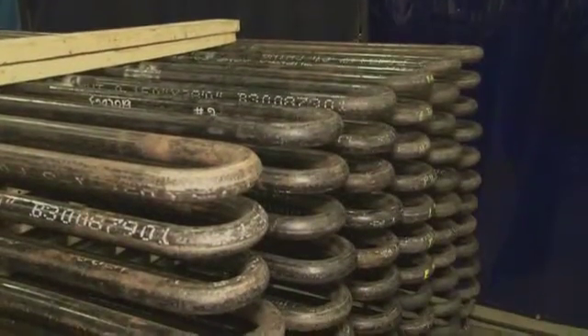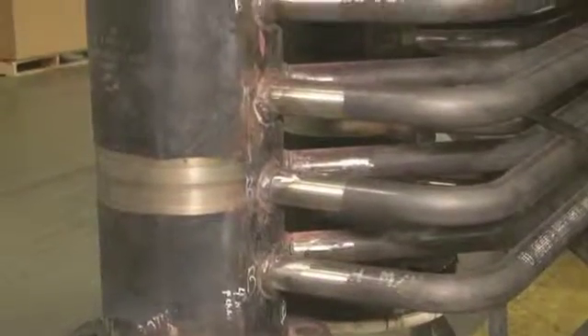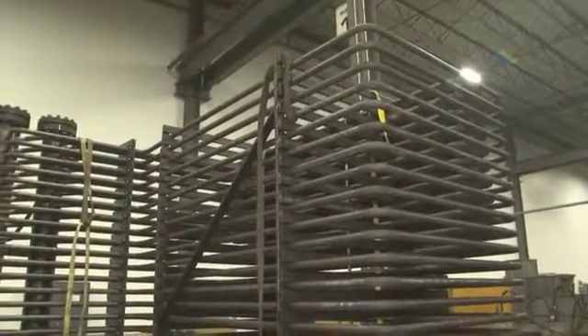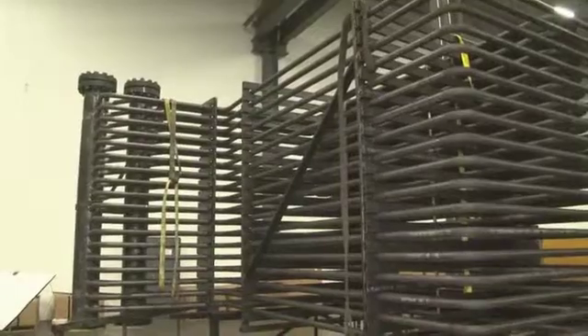After completing the pressure welding of a boiler tube assembly, the pressure welds are x-rayed to ensure integrity of the welds. Then the elements may be prepped for shipment as individual elements, or they may be assembled into a module such as the one behind me, and we will ship a completed module. In any case, the completed product is hydro-tested so that we verify there are no leaks in the boiler tube assembly prior to shipment.